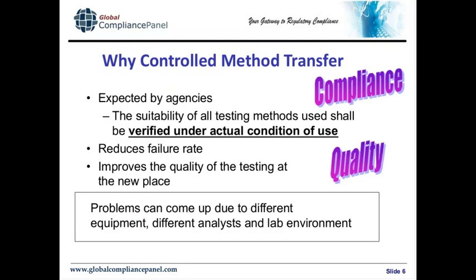This slide gives reasons why we should pay attention to controlled method transfers. There are two reasons. Number one is to comply with regulations, and equally important is to reduce failure rates and improve the quality of analytical test results — to reduce or eliminate out-of-specification test results based on inappropriately transferred methods. The main reason why transferred methods cause problems is that the receiving laboratory may have different equipment, analysts with different skills, a different environment, or different measurement practices. This is why we need to test all these things. Training is also very important — the analysts in the receiving lab should be equally well trained as those in the transferring laboratory.